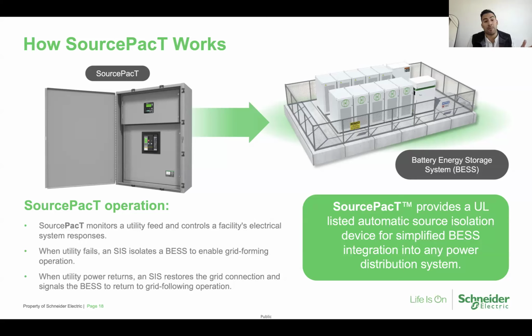But essentially disconnecting from the primary service, we send a contact signal to the battery energy storage system. Those inverters are told that, hey, we're safely disconnected. You can now enter a grid forming mode, or you can basically establish your own voltage and frequency and provide backup power. And the key benefit here is we're isolated from the primary service. We're doing that to ensure that there's no back feed upstream to utility workers in the event of outage, and you are enabling your microgrid system for resilience. You're not back feeding upstream to workers that are potentially doing maintenance work or repairs, and you're avoiding any backfeed scenarios or two different voltage and frequency sources damaging load.